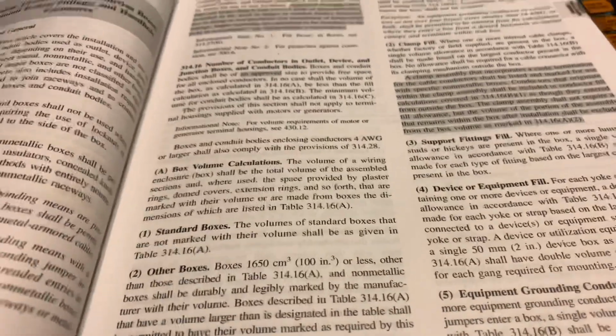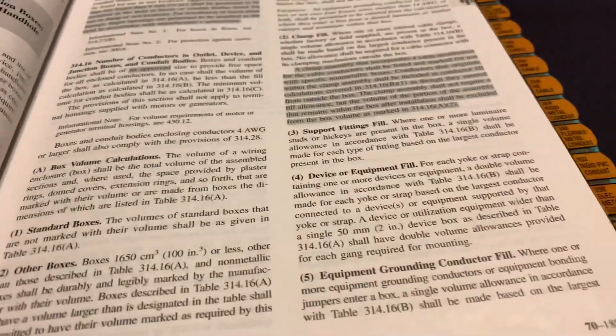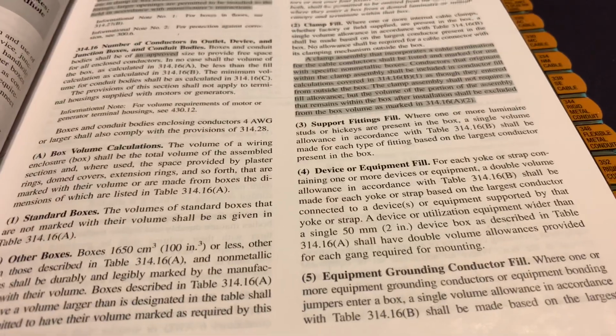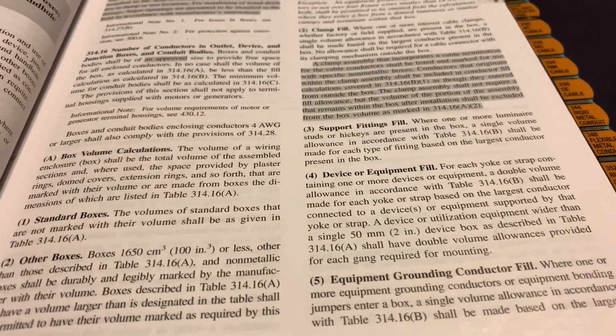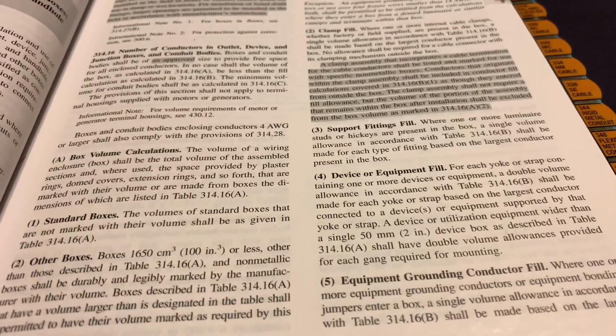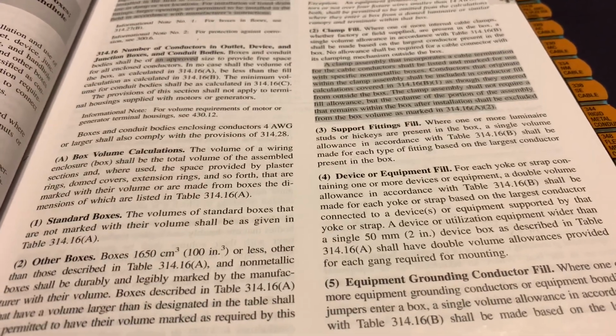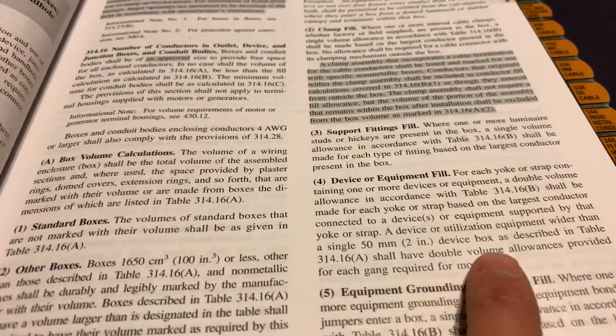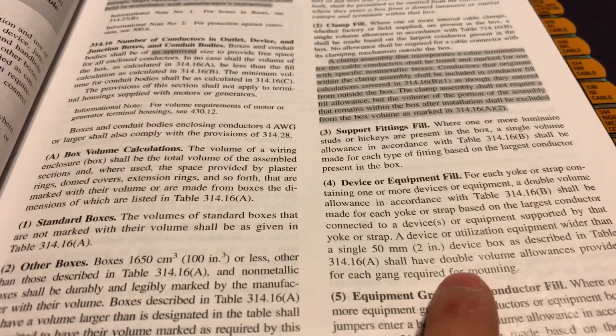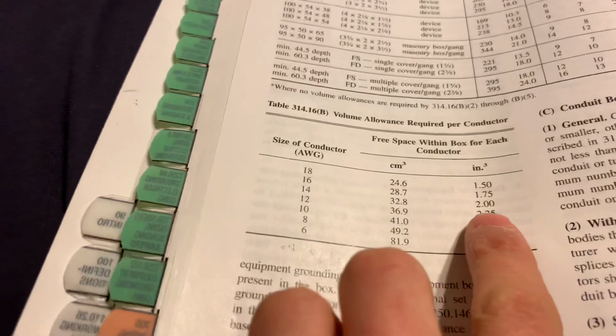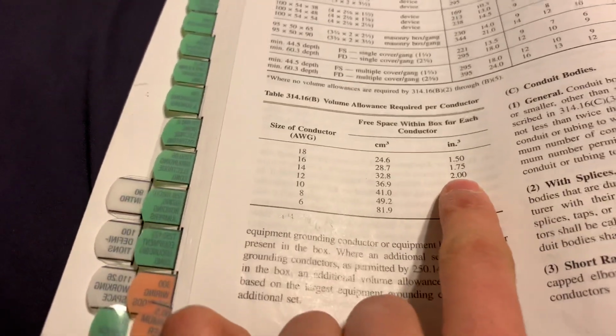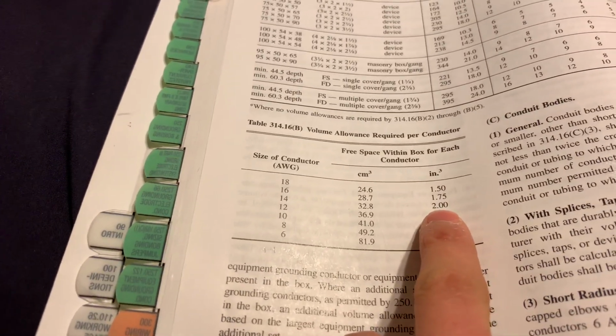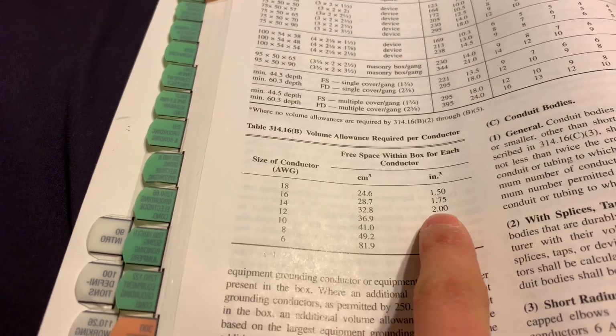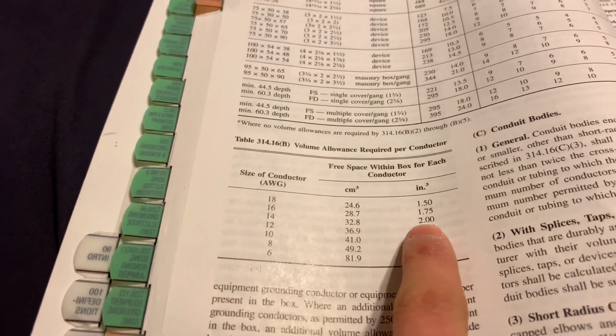So let me try to understand that real quick. I think I didn't show that on camera all the way. A device or utilization equipment wider than a single gang shall have double volume allowances. So I believe that's what it's saying. So if you have a 14 wire connected to a switch, and you have to put a switch in the box, one box, single gang, that's going to count as four.